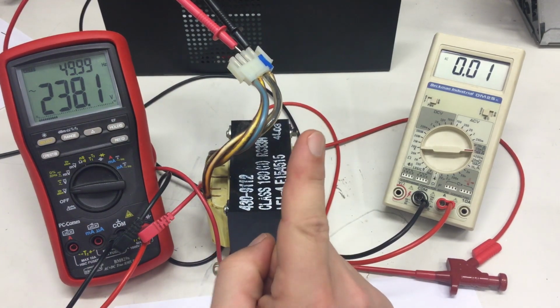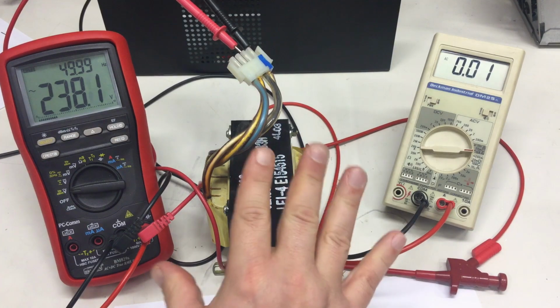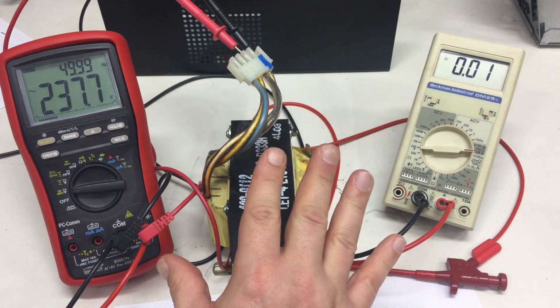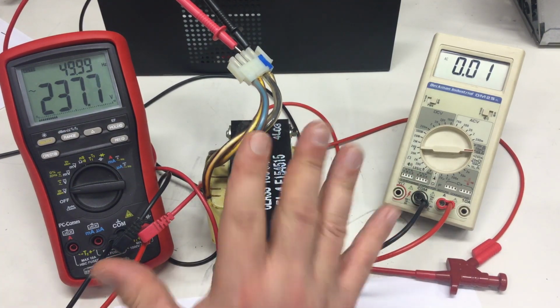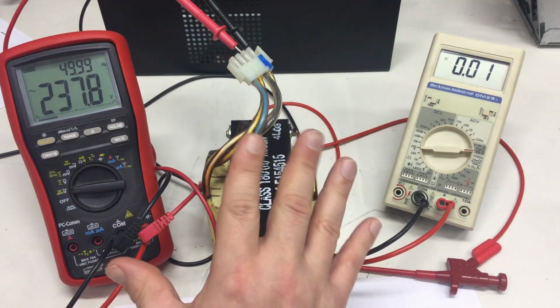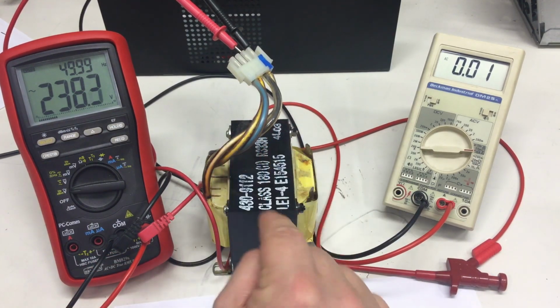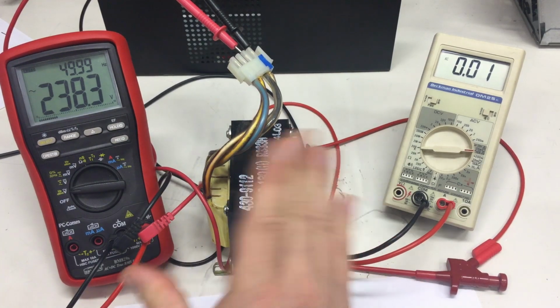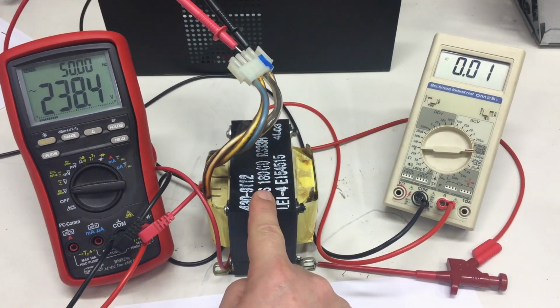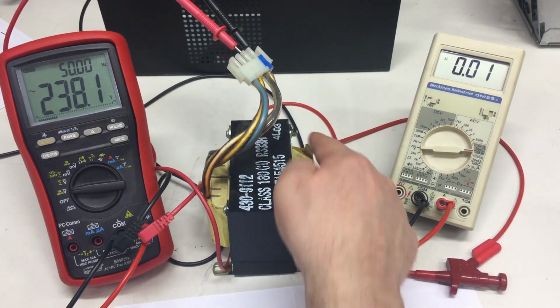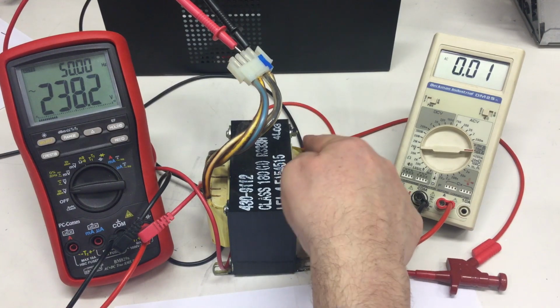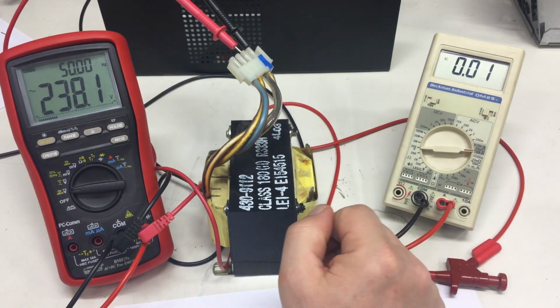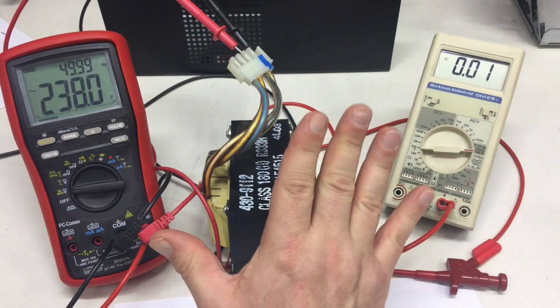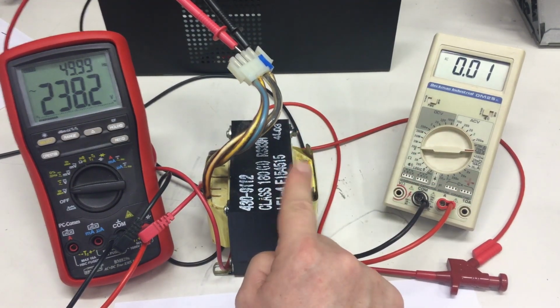And one important note: this is not a valid isolation test for transformer by any norm or industry standard. That's a hobbyist method, and the equipment you create with that, or if I use that thing in some equipment, I can't touch it now. Don't even feel a buzz. The transformer is okay. But as I said, it's by no industry standard or norm really a test for transformer.